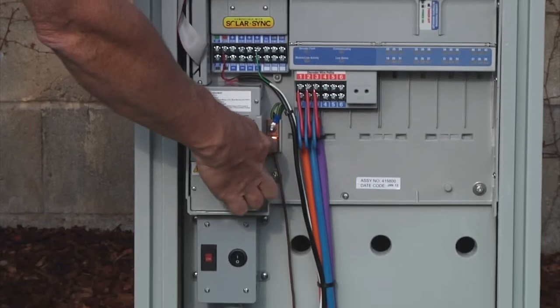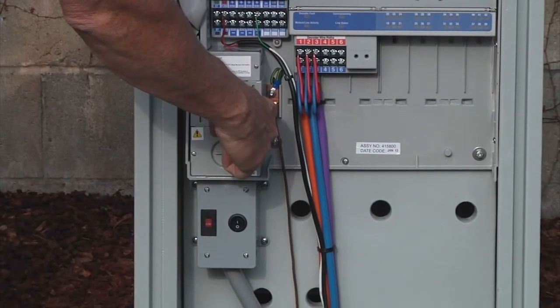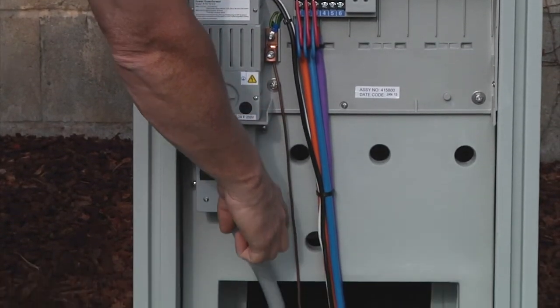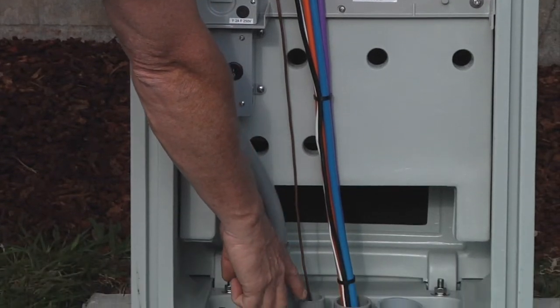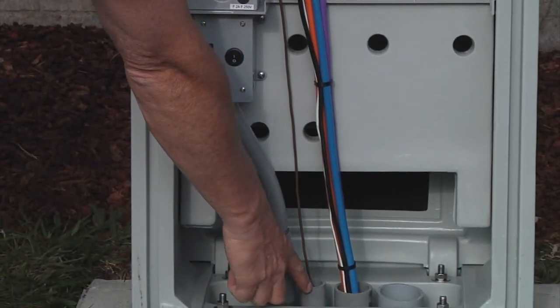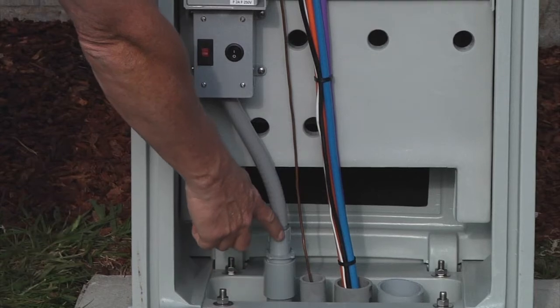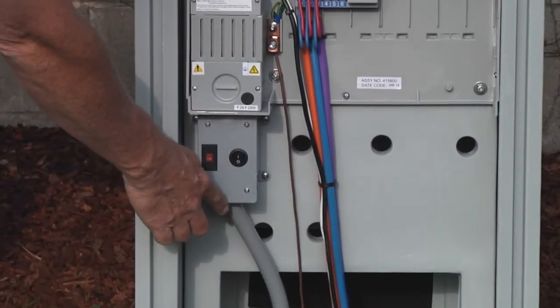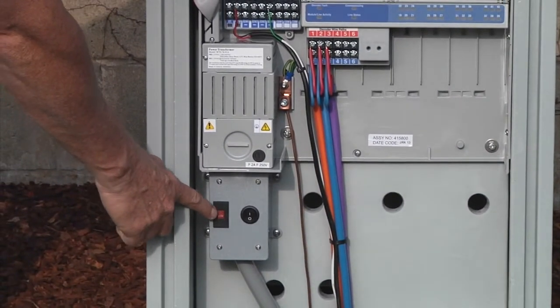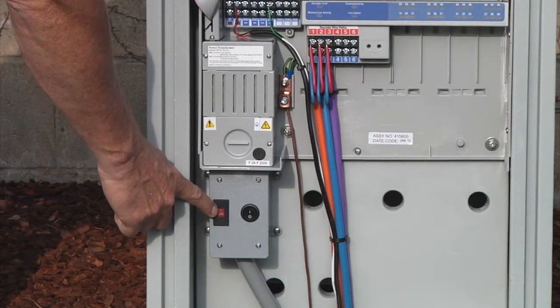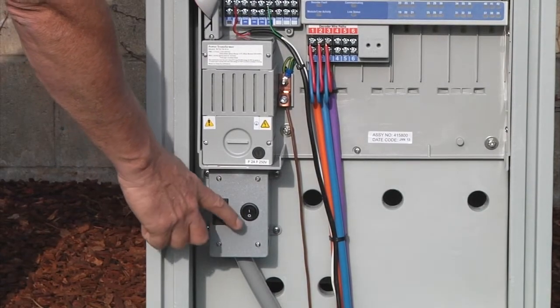To the left of that, we have the grounding lug. Now that grounding lug is for an outbound ground wire that goes out to the field to a grounding rod or a grounding plate. And to the left of that, we have the incoming power supply. In our case, it's 120. We have chosen 120 here on the selector switch. We would choose 230 in case we had 230 coming in.